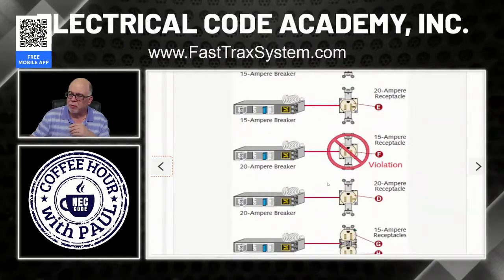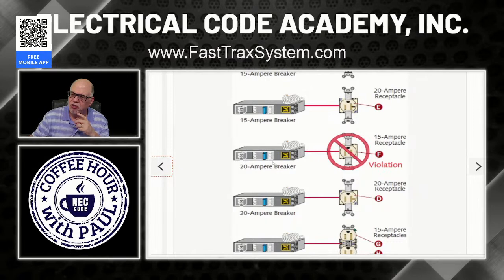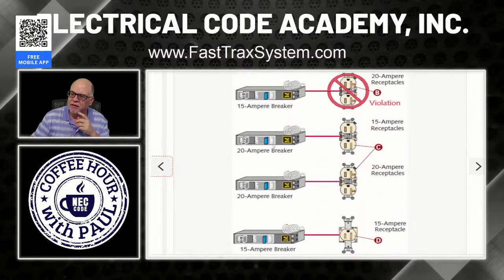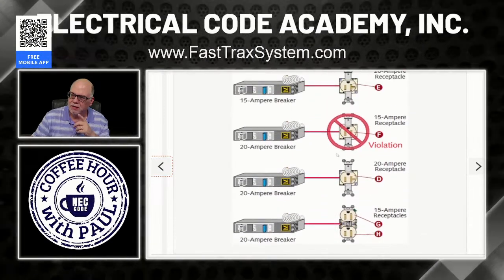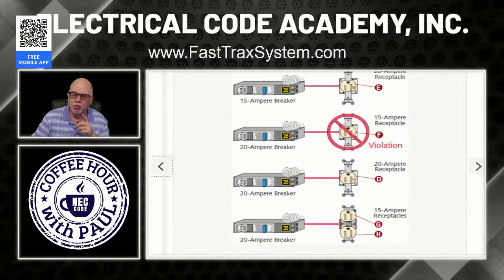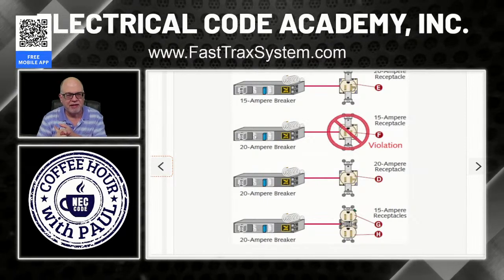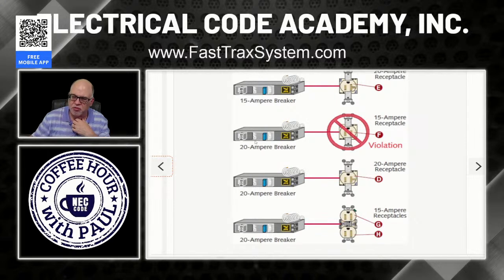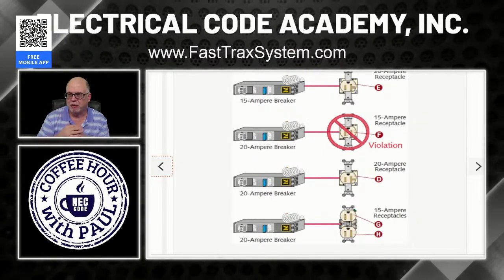All right, now here's where we start seeing those other things right here. So what about now it's a 20 amp, just like up here where it said, well, wait a minute, this 20 could be on a 15 amp, but down here, this 15 can't be on the 20. Why? Because what did it say in 210.21? It says the receptacle has to be equal to or greater than the branch circuit rating. In this case, it was 20. So that 15 is not going to work, right? Now, you could do that with a duplex, remember? You can't do it here.